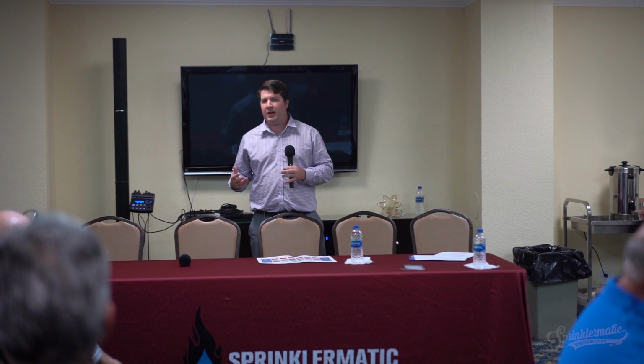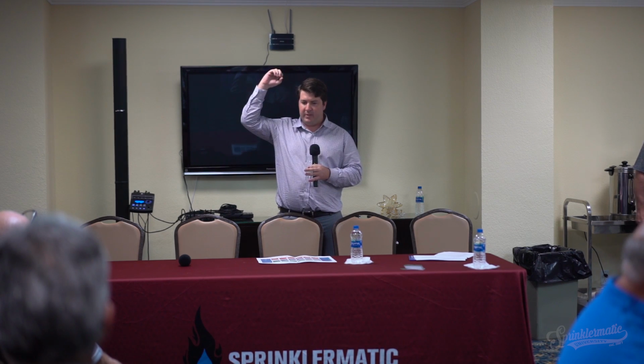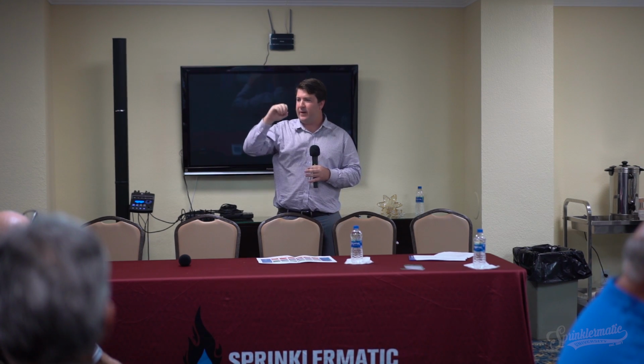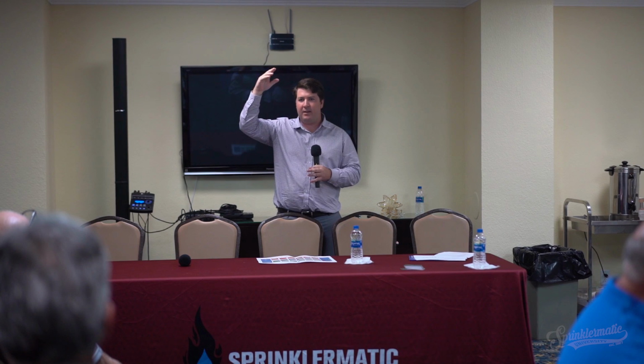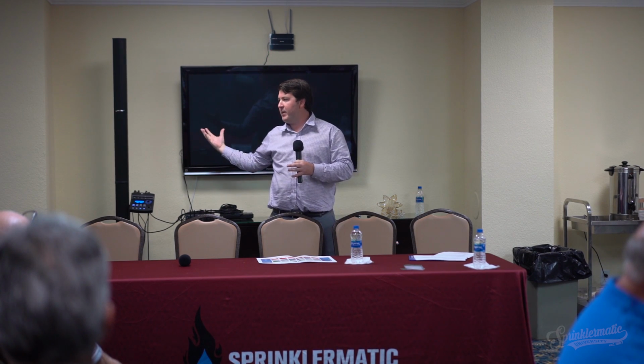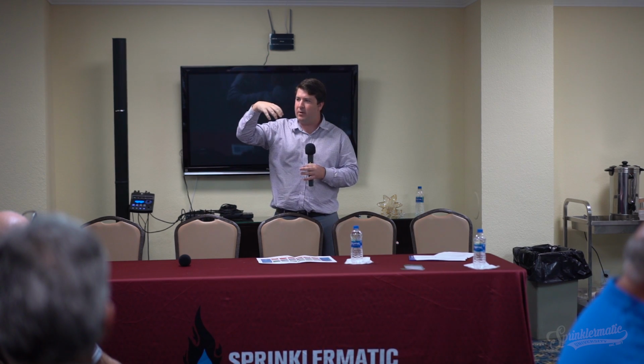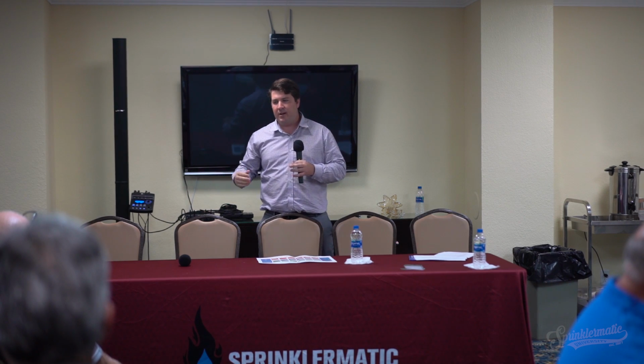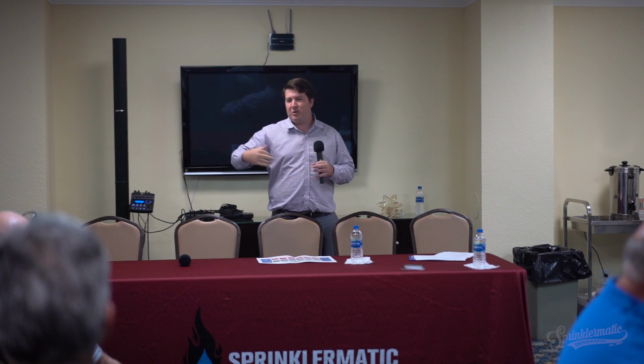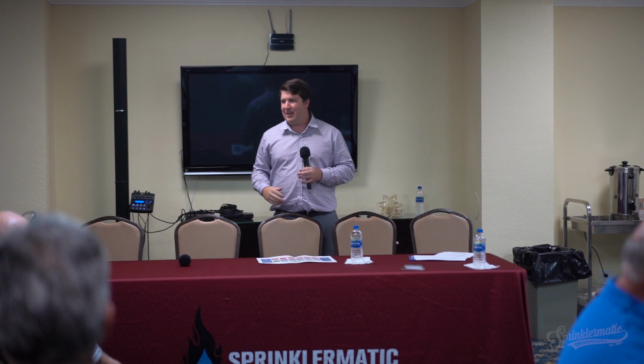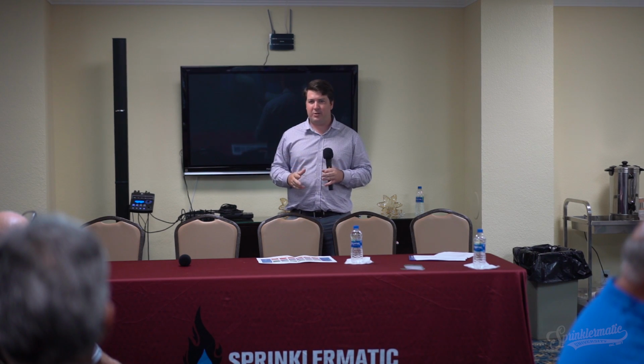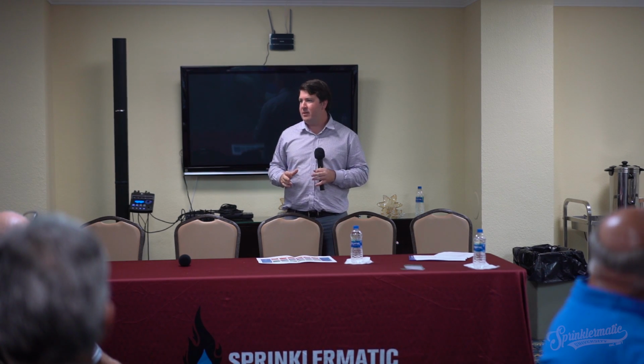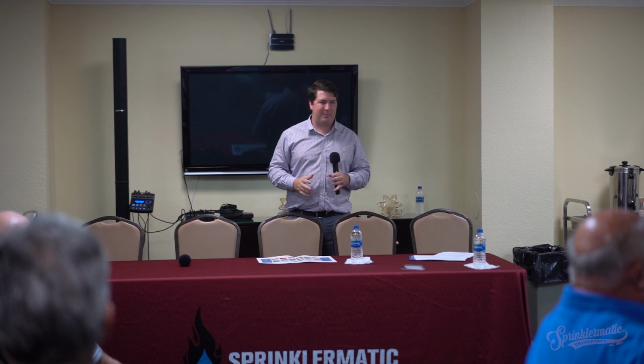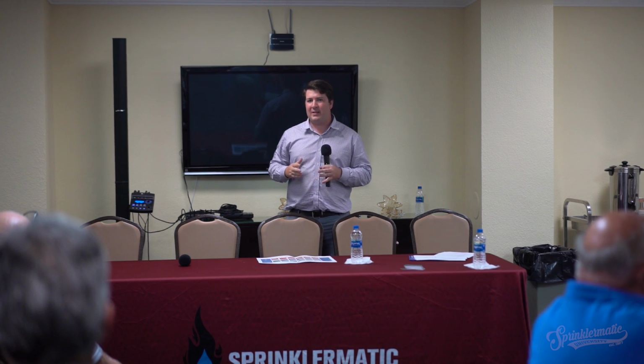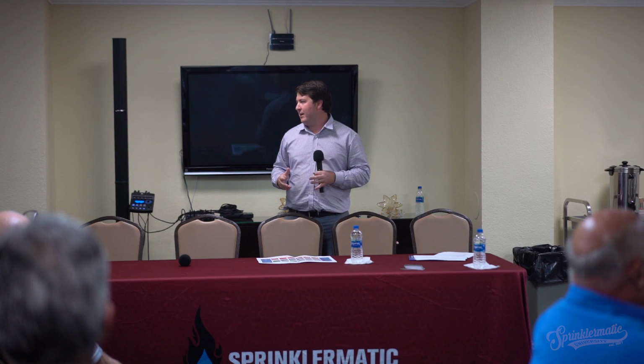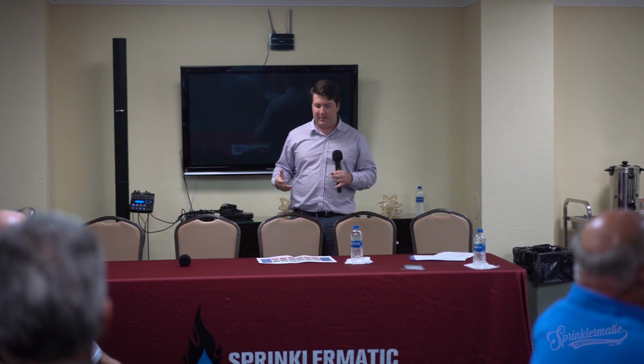It's a scary term, it's really not. What it is, it's a fan on the roof of the building that, when the fire alarm picks up smoke, receives a signal, activates, and takes air from the outside to put a positive pressure in that stairwell, so that when you open the stair door, the air blows out rather than smoke blowing in. The idea is that we encase these stair enclosures in 2-hour fire-rated concrete, but the challenge is it's not fire that typically kills people, it's smoke. And the idea is that if you get into that stair enclosure, you should be almost as safe as being outside, and that's the intent behind pressurizing it.